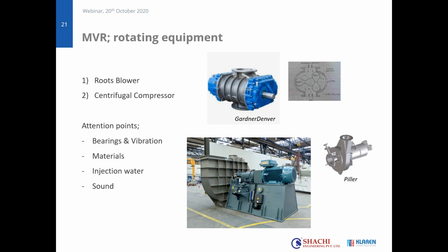But there are also some disadvantages, for example the noise it makes. If you have ever heard a roots blower run, well, in my previous company we sometimes tested one, but we always did that after office hours because everyone would hear a lot of noise. So that's the roots blower. Typically, we would use a roots blower for smaller capacities. If you go to higher capacities, then the best option would be to look at a centrifugal compressor.